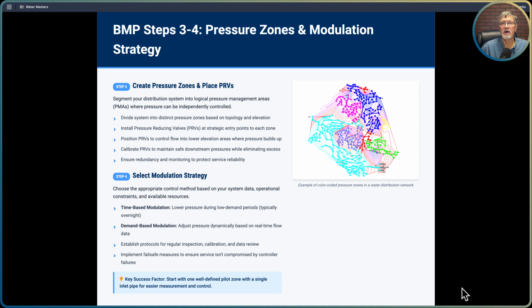All right, so now we want to select our modulation strategy. Choose the appropriate control method based on your system data, operational constraints, and available resources, and basically, what you can afford is what some of this step comes down to. We've got a number of approaches here. Most small systems now basically just have a PRV that is set at one pressure, and we don't adjust that much. So we want to go to adjustable pressure. There's a number of techniques to handle that.